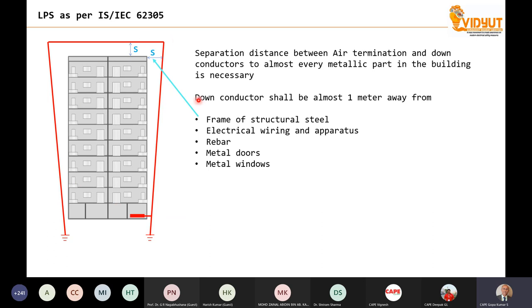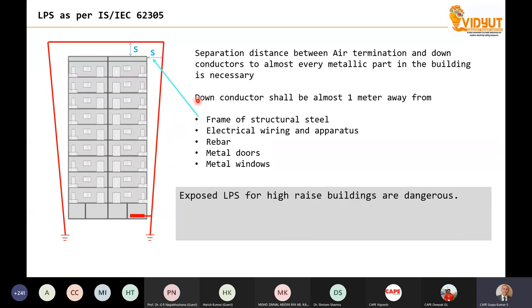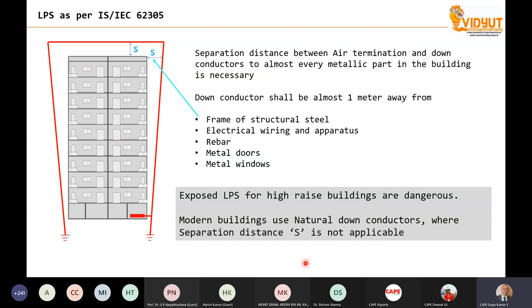So this is also an important subject which needs to be considered in the case of a lightning protection system. In modern buildings, natural down conductors, natural down conductor means the rebar, with a little bit of modification, the steel rebar itself is used as a down conductor. As a result, the separation distance we are supposed to avoid. We need not calculate the separation distance in a modern building.